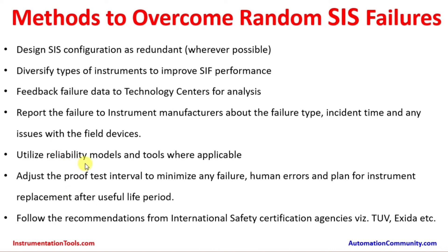Additional methods include utilizing reliability models and tools where applicable, and adjusting the proof test interval to minimize failures and human errors. Plants should plan for instrument replacement after the useful life period. Some plants perform maintenance at regular intervals and replace components such as o-rings during major turnarounds, while others may skip this due to time or economic limitations — which increases the chances of equipment or valve failure.